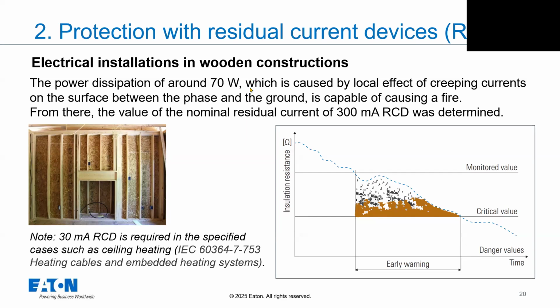After calculating from 70 watts to current, the limit was fixed at 300 milliamps, as it is. The idea behind this is described in this picture. At the moment when insulation resistance is going down, for example humidity is growing or there is some damage, we need to detect this creeping current and disconnect the supply. Usually it is 300 milliamps, but for special cases, like in part 7-753 of the standard, heating cables and heating systems, it's only 30 milliamps.